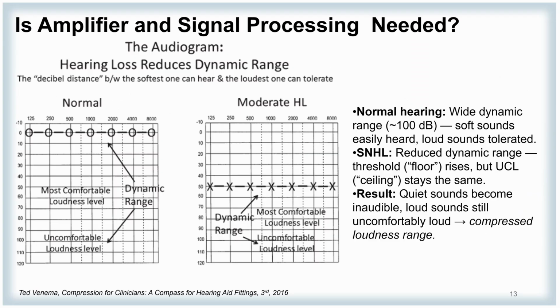So in normal hearing, we have a wide dynamic range from 0 decibel to about 100 decibel. It's a dynamic range of 100 decibel. But in sensorineural hearing loss, this range becomes compressed. So soft sounds are inaudible, but loud sounds are still uncomfortable. So we need a specific type of processing. We just don't want to amplify the signal and give it to the patient, because that will become uncomfortable, as loud sounds are still uncomfortable. This is why hearing aids use dynamic range compression.